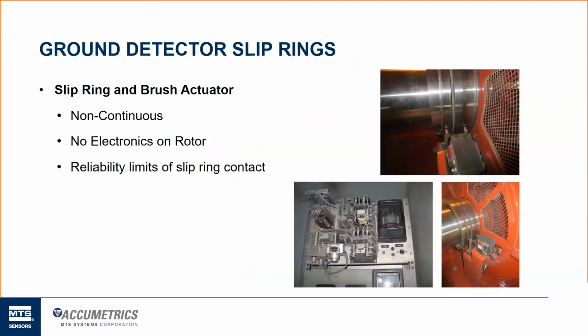So here's the more traditional way to get access to the rotor. It's a slip ring approach where they press fit these slip rings. I don't know if you can see to the right where my cursor is. So one of these slip rings is connected to the steel of the machine itself, or rotor ground, and the other one would be to the negative side of the field. When I talk about the negative and positive side of the field, all that basically means is one side of the field windings versus the other. So those copper bus bars run out on the generator and form many thousands of feet of windings, and one side would be referenced to negative and the other side would be to the positive side of the field.